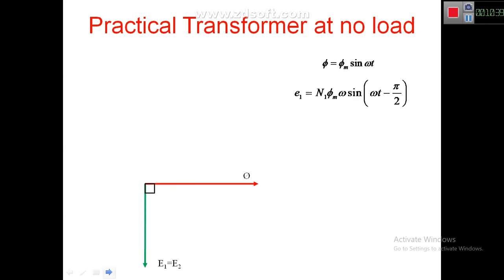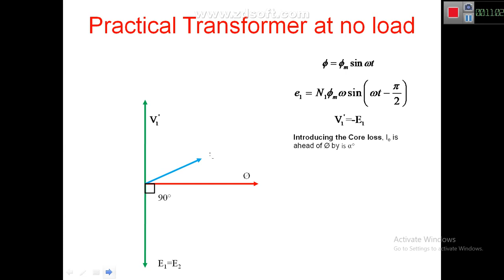This fact is incorporated in our practical transformer at no load. Flux phi is drawn as reference; EMF is 90 degrees behind the flux phi; V1' equals minus E1. Now introducing core loss, Ie is drawn alpha degrees ahead of flux phi. Ie is divided into two components: Ic — the core loss component — and Im — the magnetizing component — shown as phasor addition: Ie = Ic + Im.